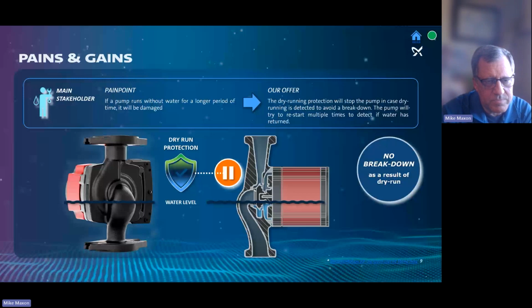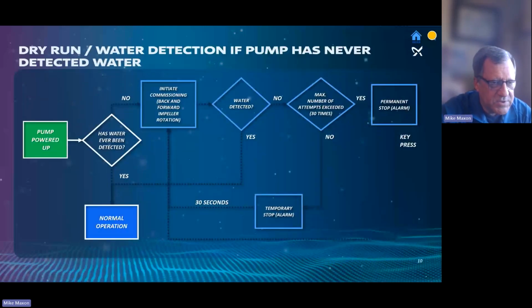The dry run protection. Dry run has been known as the most common reason for a pump to break down, the most common reason for a pump to fail. And with this dry run protection, this is the algorithm that it goes through. What it'll do is test for whether it's never seen water before, first time installed. It does know the difference. It will check for water. If it sees water, fine, it'll run.